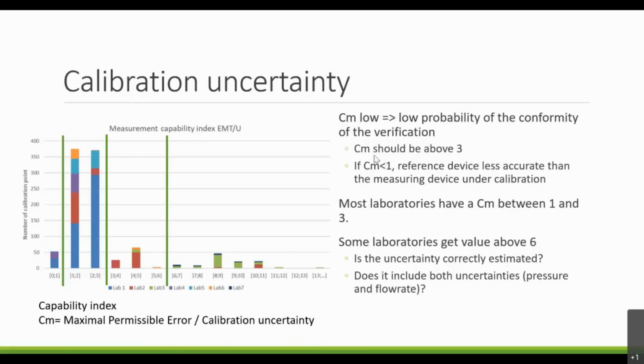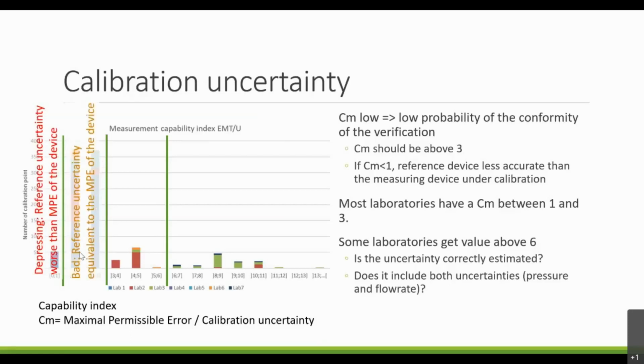If it's below 1, it means that the reference device used is less accurate than the measuring device under calibration. And we have some data here below 1, so it's quite depressing, because that means that the reference is worse than the device under calibration. We see here that most laboratories have a capability index between 1 and 3, which is quite bad, because it means that the reference uncertainty is quite equivalent to the MPE of the device.